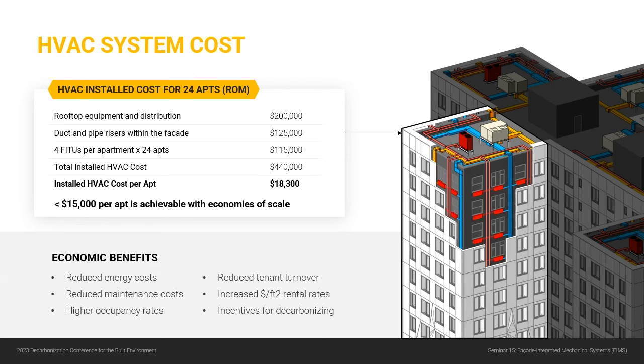Okay. Now, if all that sounds great, you're probably still wondering, okay, but how much does it cost? So let's talk about the economics. We're again going to look at one wing of a building. So this is going to be a rough order of magnitude for a system serving 24 apartments. If you look at the cost of the rooftop equipment, the duct and the pipe distribution, and all the FITUs, you would get a total installed cost of about $440,000. When you amortize that over 24 apartments, it's about $18,000 per apartment.